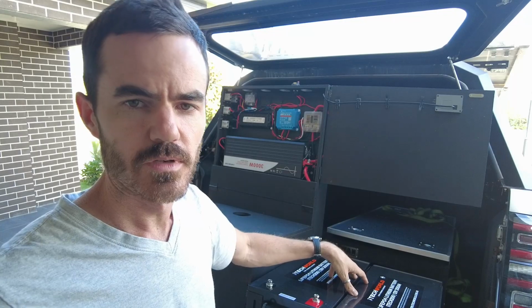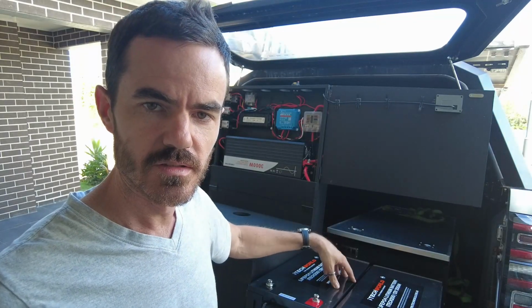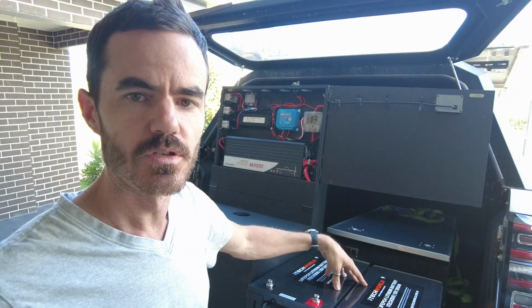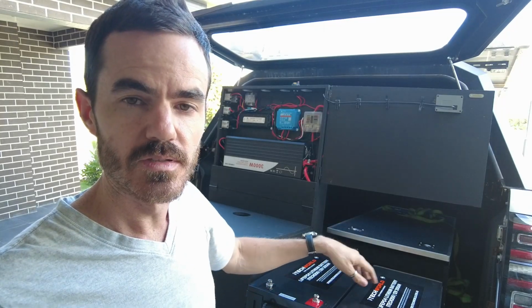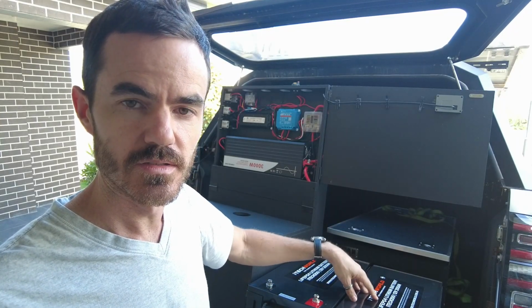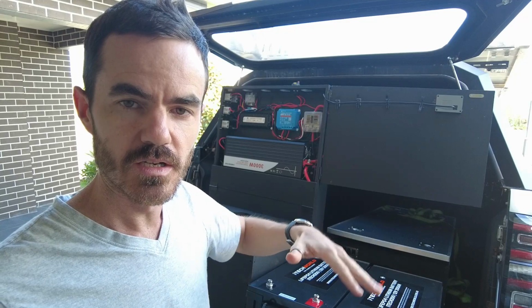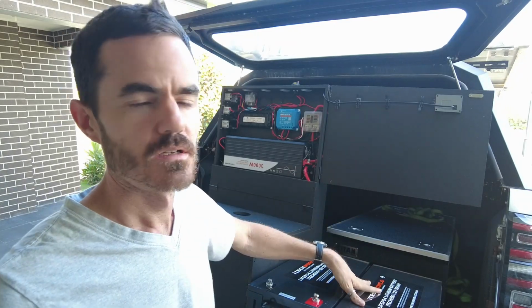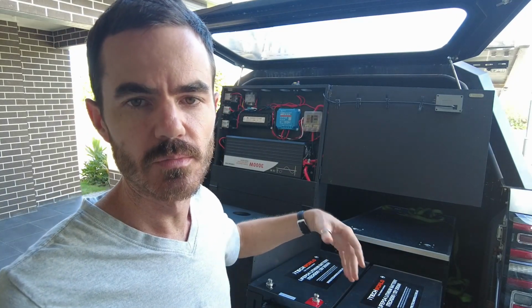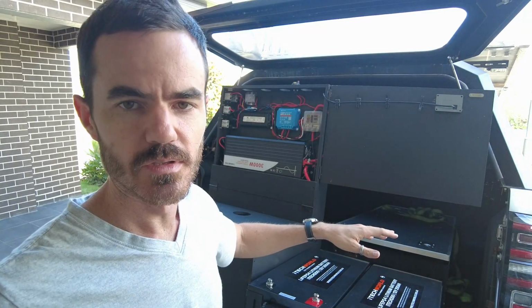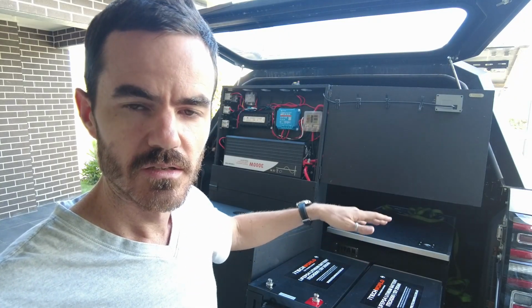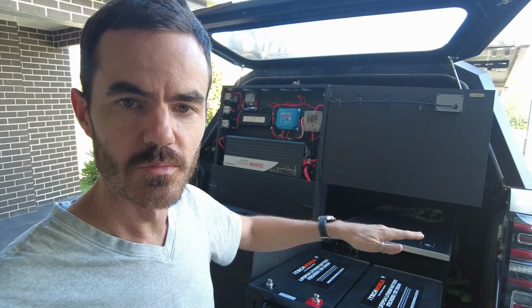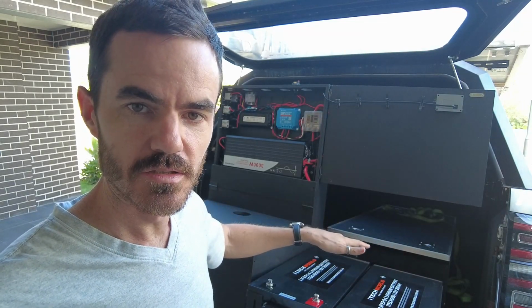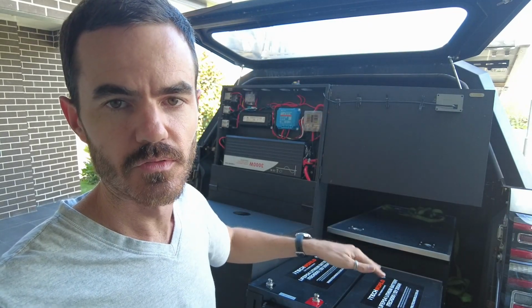So when you're running lithium phosphate batteries in series, you need to make sure that they are fully charged. You want the state of charge to be the same on the batteries before you connect them in series. That way, when you charge and discharge, it'll keep them nicely balanced. Otherwise, if they're not the same state of charge when you hook them up in series, you'll have problems when charging and discharging. Only one of them will fully charge, or one will cut out before the other one's discharged, etc. So they need to be nicely balanced before you put them together.